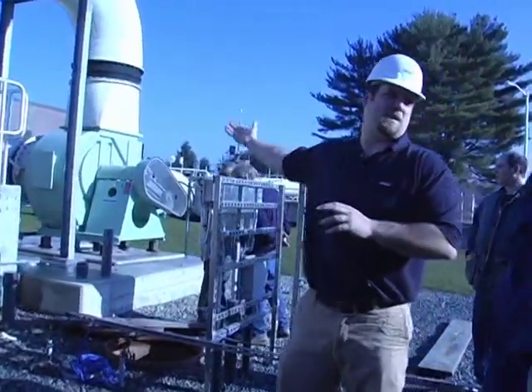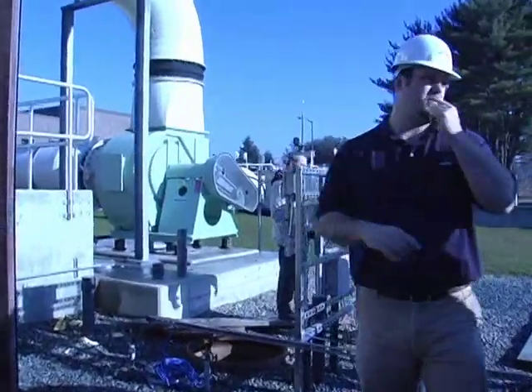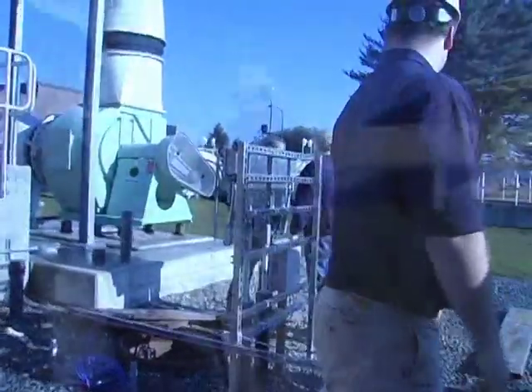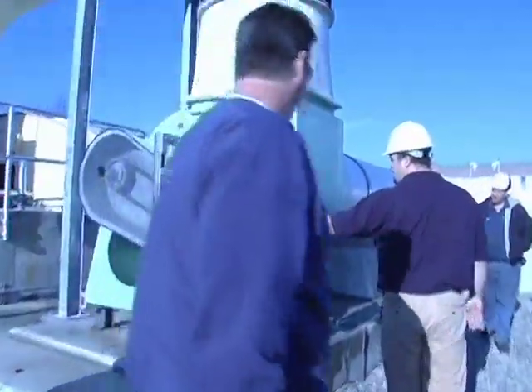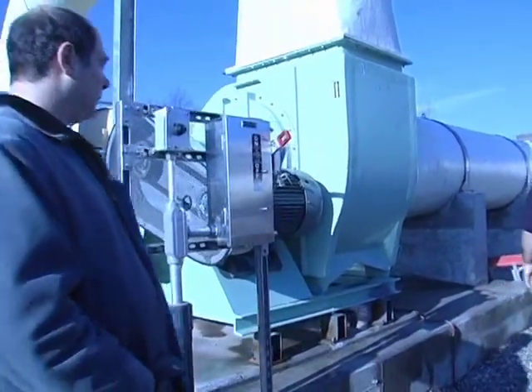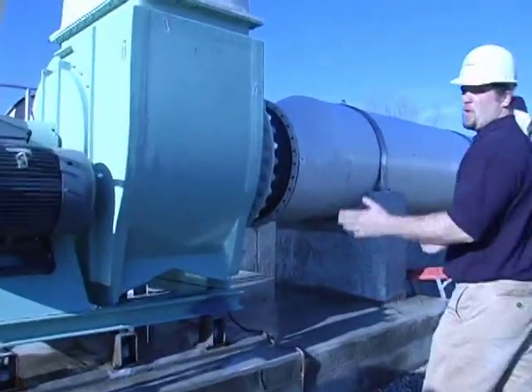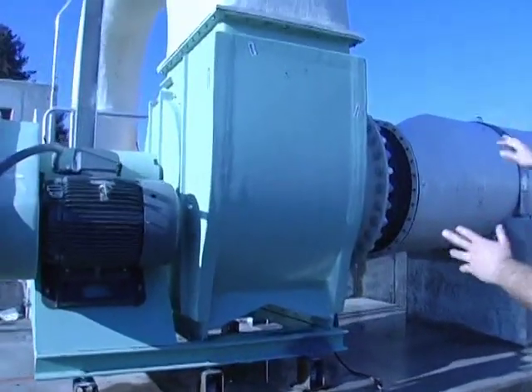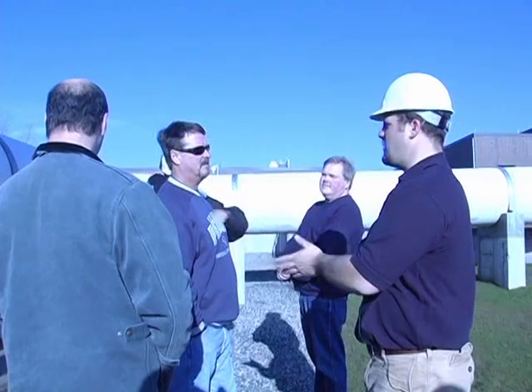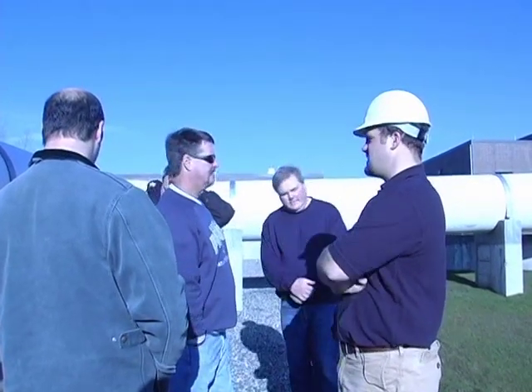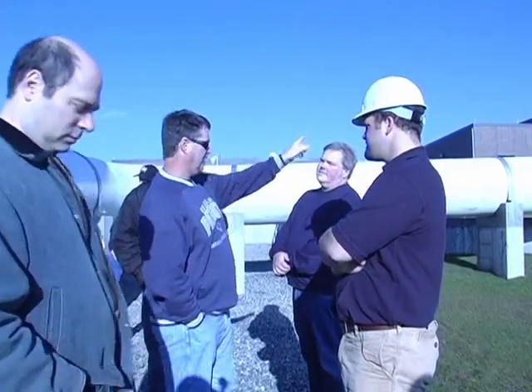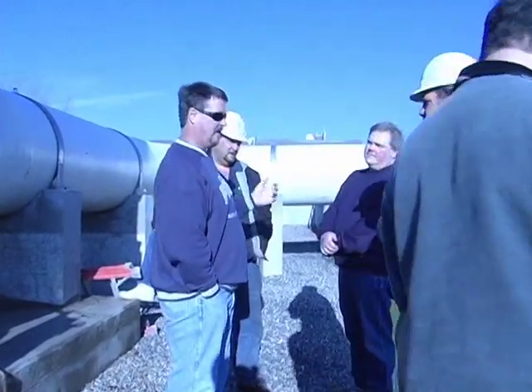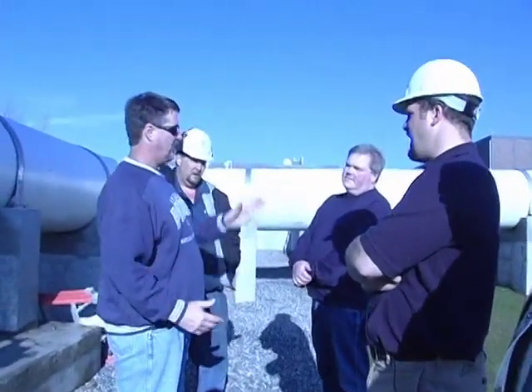And there's the drain traps coming up through the ground over on this side here, where the drains would be cleaned. So this is the main blower feed power here. And again, everything should be locked out, tagged out. There should be no air going into the system at all if anybody's underneath those covers doing any sort of maintenance. Regardless of anything else, this blower is balanced right now. When it turns on, it will pull 18,000 CFM regardless. So suppose he wants to open a manhole over there, when he opens it up, it could be like a wind tunnel down there.